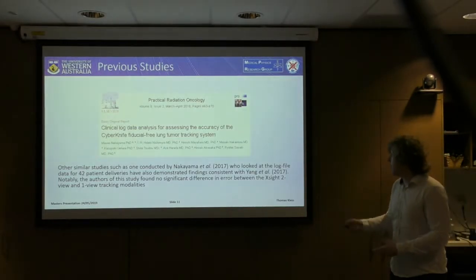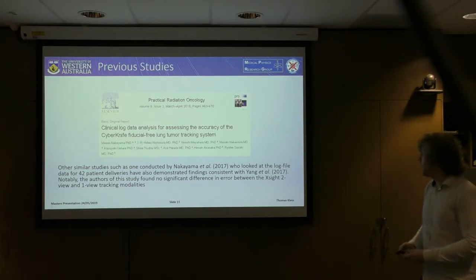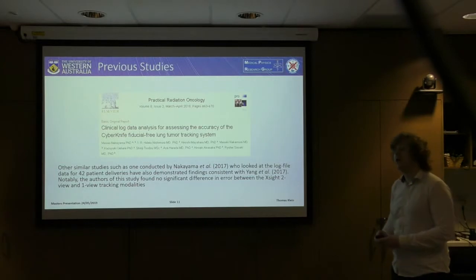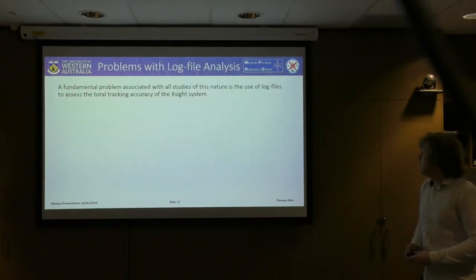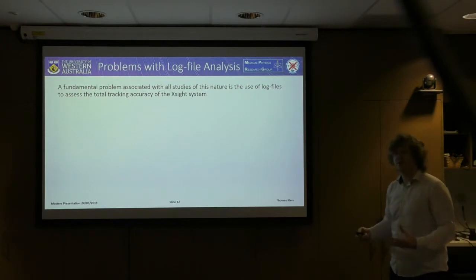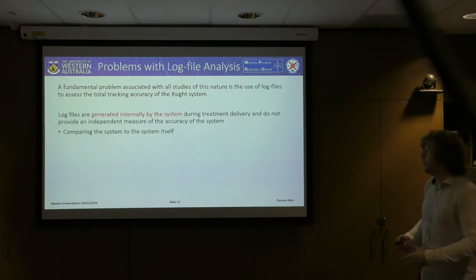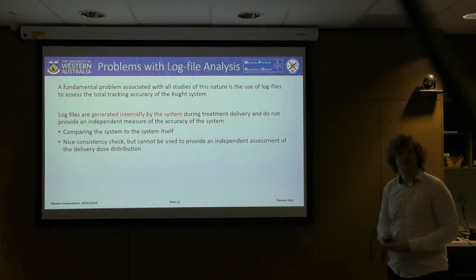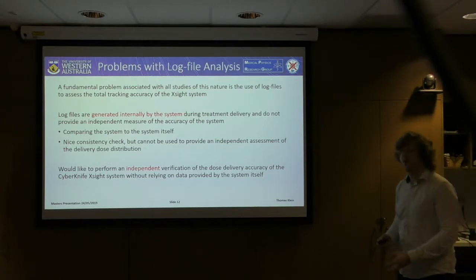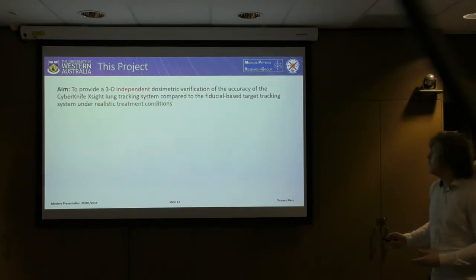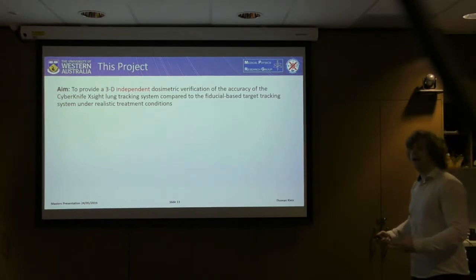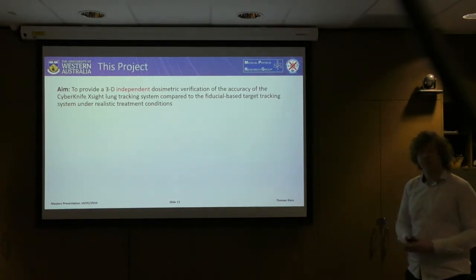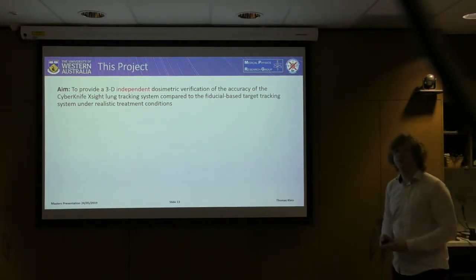There is a fundamental problem with all such log-file-based studies: the log files are generated internally by the system during treatment delivery, so it is essentially comparing the system to itself. It's a consistency check, but cannot provide an independent assessment of delivery dose accuracy. Therefore, we wished to perform an independent verification of dose delivery without relying on any treatment parameters provided by the system itself. This brings us to the main aim: to provide a three-dimensional independent dosimetric verification of the Xsight system compared to the fiducial-based target tracking system under realistic treatment conditions.